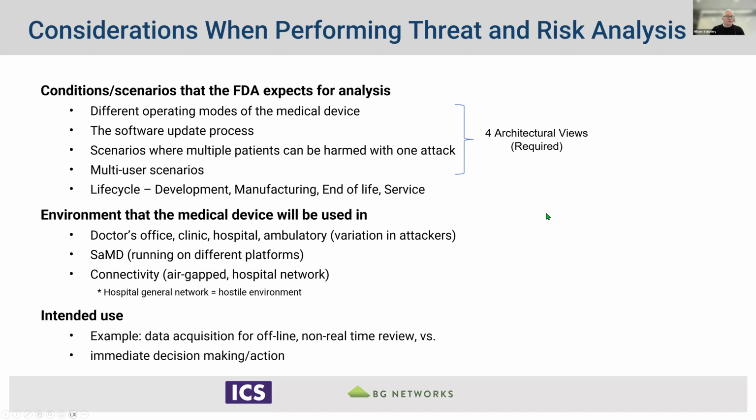And lastly, the intended use. You can envision the considerations would be drastically different if this is a device for, say, data acquisition for offline, non-real-time review versus something that's actually used by clinicians in immediate decision making.